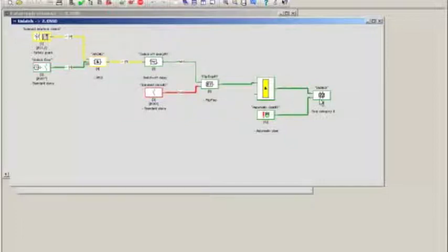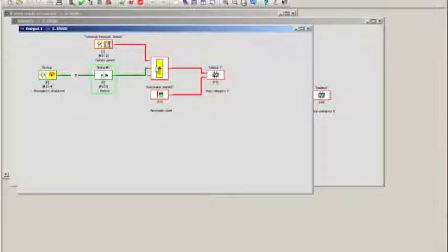You already heard that in the background the safety contactor dropped out. The reason is that the mechanical construction of this particular door lock switch that I'm using here is such that when the coils are pulled in, the switch will provide a false signal. And false is, again, on this screen, here. The interlock switch will in fact turn off. So as soon as that turns off, of course my motor contactor will drop out.